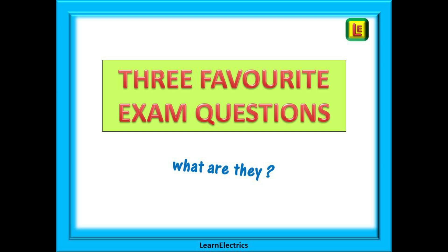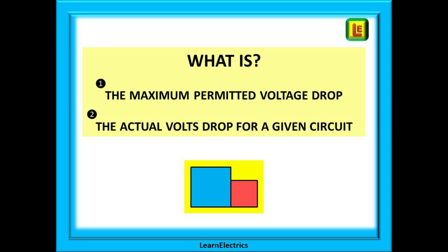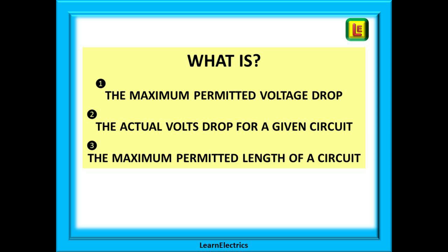You will need a calculator but nothing more difficult than multiply and divide. The three question types are: number one, what is the maximum permitted voltage drop; number two, what is the actual volts drop for a given circuit; and number three, what is the maximum length of cable that can be installed to not exceed the maximum permitted voltage drop. And that's it.